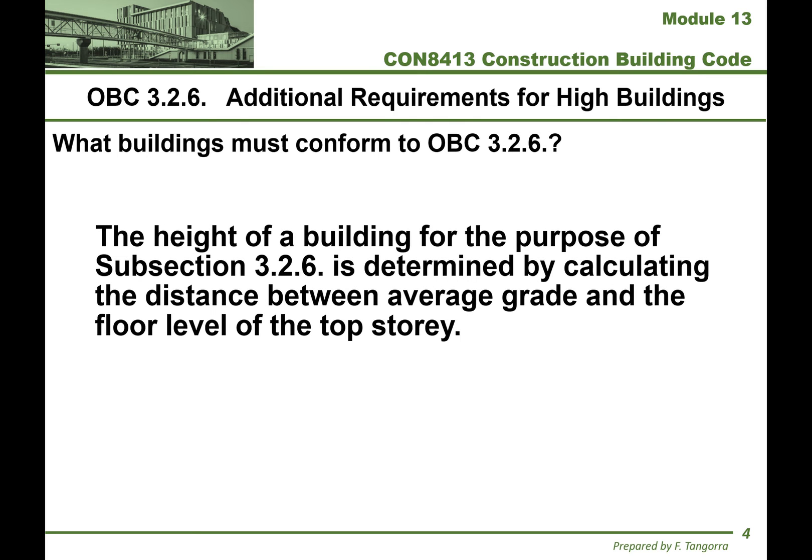What buildings must conform to 3.2.6? There are specific types of buildings that meet a height requirement, and the height is calculated as the distance between the average grade all the way up to the floor level of the top story — not the ceiling level of the top story. Basically, you're measuring the vertical distance between the outside average grade of a building and the highest point where people will be standing, which is the floor level of the top story.